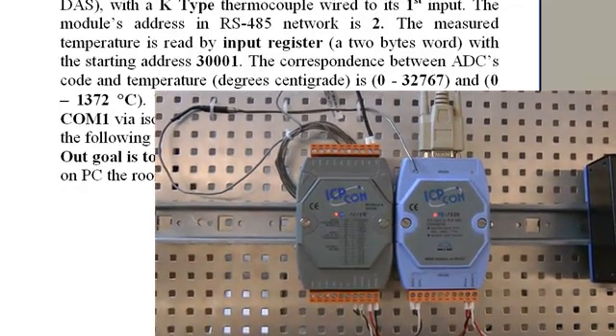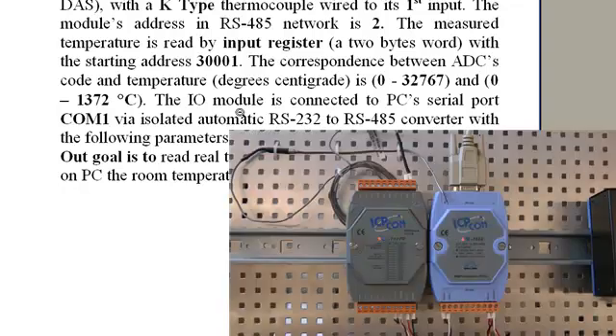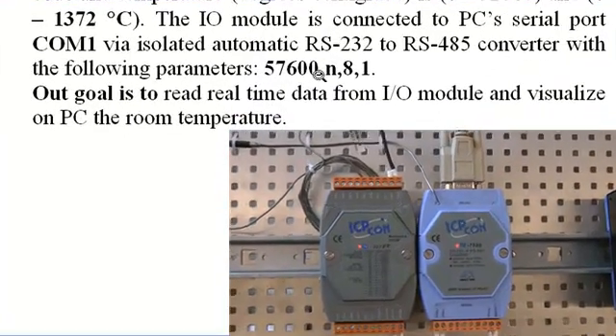The I/O module is connected to PC's serial port COM1 via isolated automatic RS-232 to RS-485 converter with the following parameters: 57600, n, 8, 1.